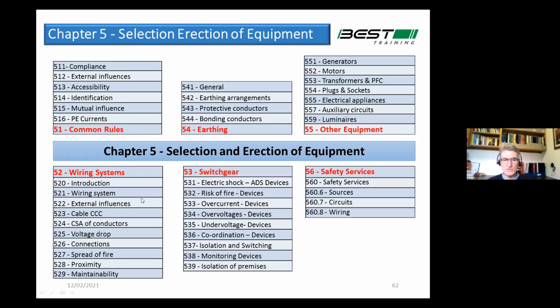So Part 52 is wiring systems. It covers the different types of wiring systems, cable management, current carrying capacity of cables, the approach for sizing the cable, some standard cross-sectional areas of conductors. Then it goes into voltage drop, which, you know, they've removed the voltage drop tables. I mentioned that earlier on, and replaced it with a formula, a very complex formula.